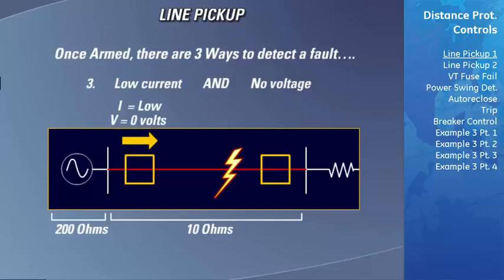Extra care must be taken when the trip output is used on weak systems such as this, because the pickup setting of the line pickup instantaneous overcurrent element needs to be set very low. Upon closing the breaker, normal inrush currents would cause this element to trip if the voltage level were slower to build up than the current. For this reason, an additional blocking delay has been added to the line pickup element that allows enough time for the voltage to rise to its steady state before the element is allowed to trip.